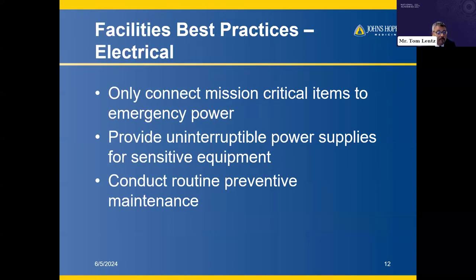This is a bit of a misunderstanding for many folks, but when things are on generator power, it doesn't mean you always have power. If you lose normal power at the outlet, it generally takes between 5 and 10 seconds for the generators to come online, synchronize, and provide power to that outlet. If you have sensitive equipment - computers, controllers for HVAC equipment, whatever it may be - they will lose power for 5 to 10 seconds unless you provide a UPS, which acts as a battery for those few seconds and gets over that hump. It buffers until power is available back to that outlet.